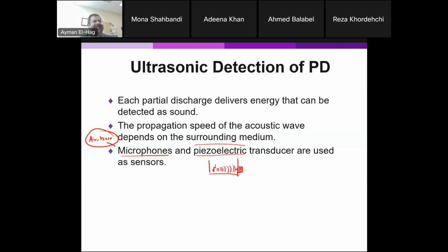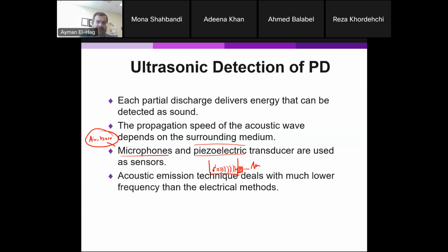They are very, very sensitive. Because of the partial discharge, those waves hit the tank, there will be some vibration of those sensors, and this will produce an ultrasonic wave in the form of a voltage. So you go and detect it, and this is how you can use it. This is the piezoelectric. If you have a transformer, a GIS system as well, anything enclosed in a tank, then you have to use a piezoelectric sensor. Anything airborne, then we use the microphones.